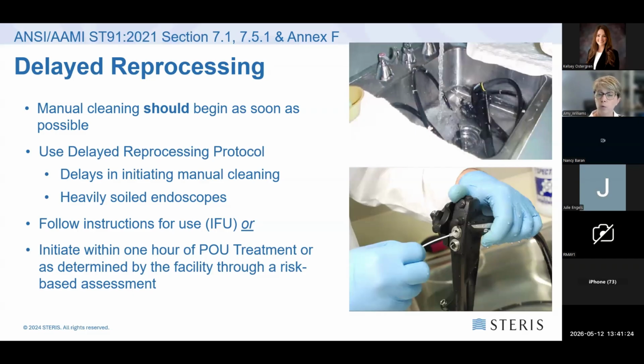Even if point of use was done and done well, we still don't want that scope to sit more than an hour. Sometimes the IFUs will say begin manual cleaning within 90 minutes. In some cases, I've seen them say 120 minutes. So you have to think about the principles of biofilm growth and what's safest. That's a facility decision. You write that into your policy. So you do need to refer to the IFU and then consider all of the infection control principles around biofilm. Okay. Delayed reprocessing should be specified in the IFU. It should tell you exactly what steps need to occur if you are going to do a delayed reprocessing cycle, and those should be followed. It might be a longer soak. It might be extra brushing, whatever the IFU specifies. But it should be followed if manual cleaning can't begin within that one hour time frame. Okay.